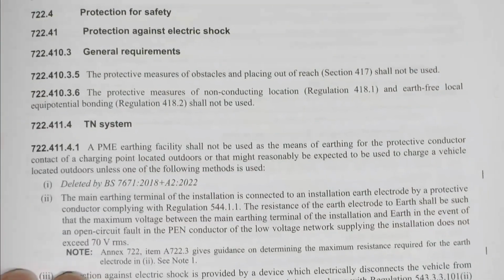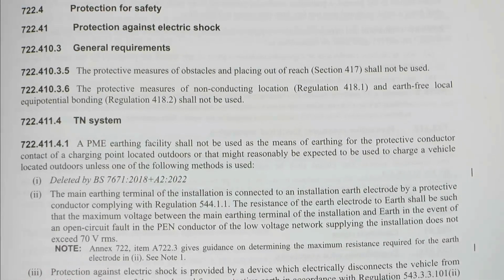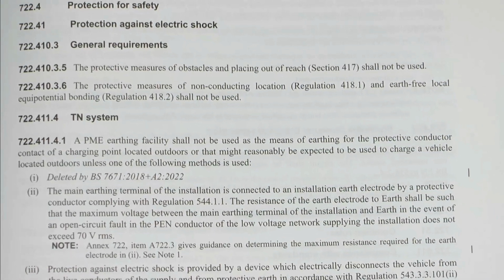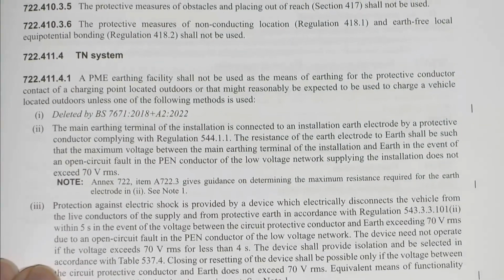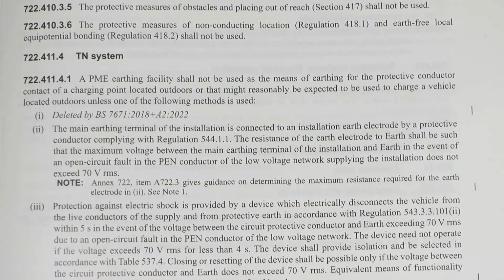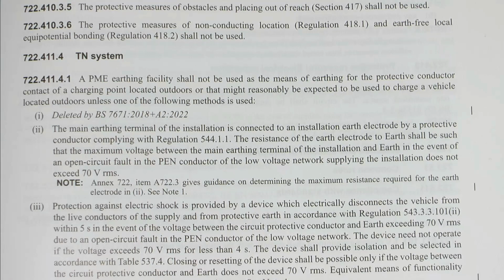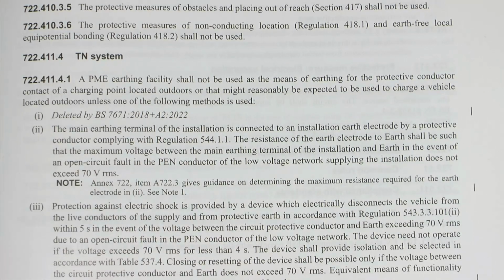However, if we move down here, under protection for safety, general requirements, TN system, this is where a PME earthing facility shall not be used as the means of earthing for the protective conductor of a charging point located outdoors, or that might reasonably be expected to be used to charge a vehicle located outdoors - which is basically all of them - unless one of these is used. Previously there were 5 of these options, and item 1 is what's been deleted. So you can't use that number 1 anymore. This doesn't really make a lot of difference because nobody was actually going to use this anyway.